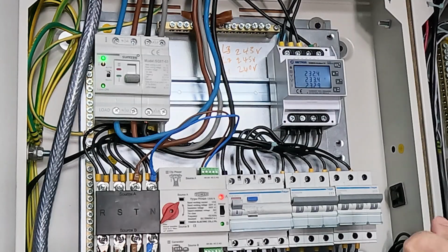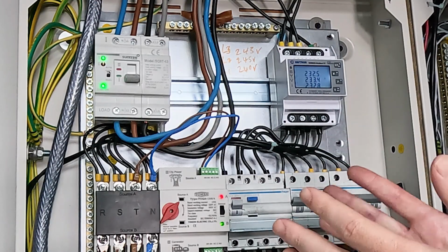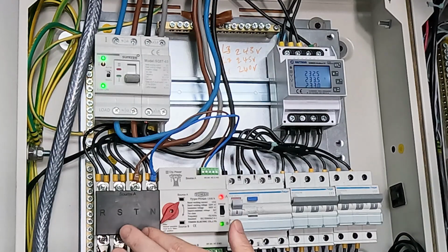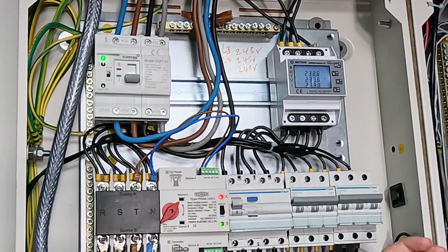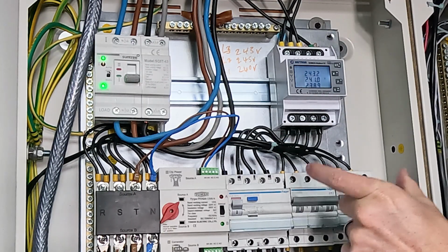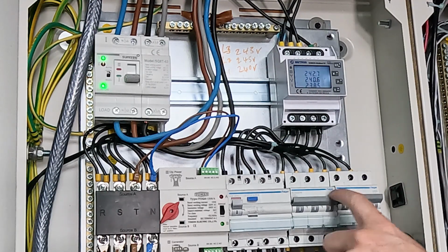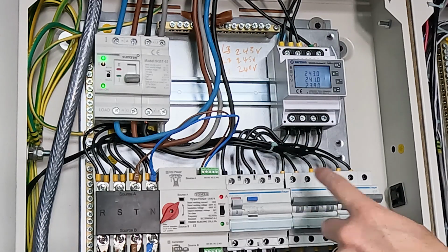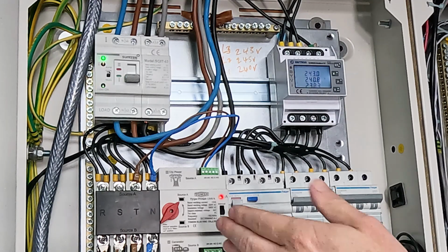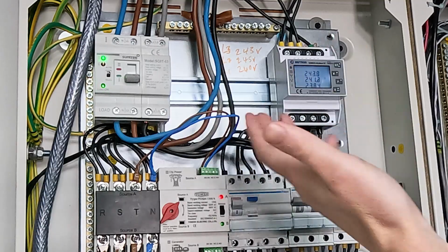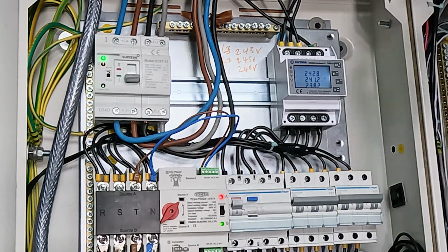Now, just to simulate something else, as I highlighted earlier, there were two major advantages to having this ATS. The one is that you can have more power, so effectively I can have 125 amps through the system. And the other major advantage is if your inverters fail, if your batteries fail, if solar panels fail, if anything goes wrong, if these breakers trip, it will detect that there's no voltage on the backup, and it will transfer back to the grid voltages. So this system is finding where there's voltage on either, and it's transferring to the one where there's voltage.